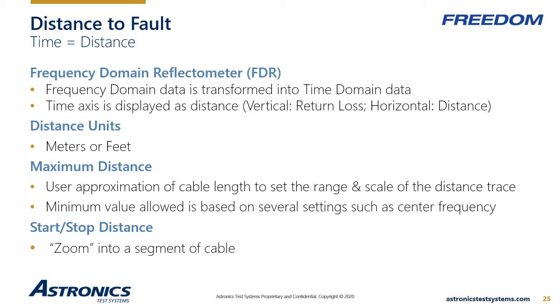The user selects the distance units of measure of feet or meters. The user tells the instrument how far down the cable to sweep. This is typically set to a value just longer than the approximated length of the cable. Once the cable is swept, the user can focus on a cable segment that may show a potential issue by setting the start and stop distances.